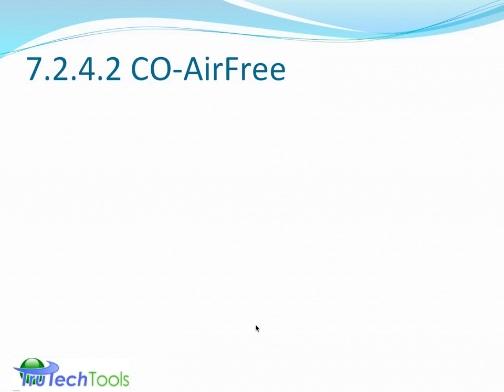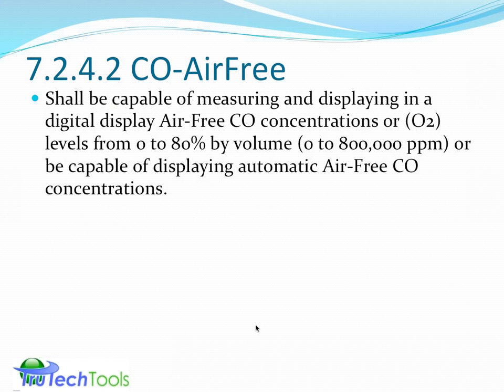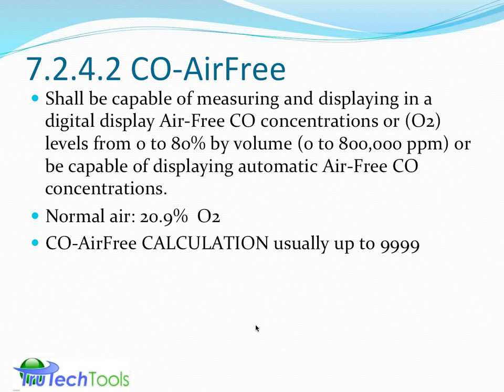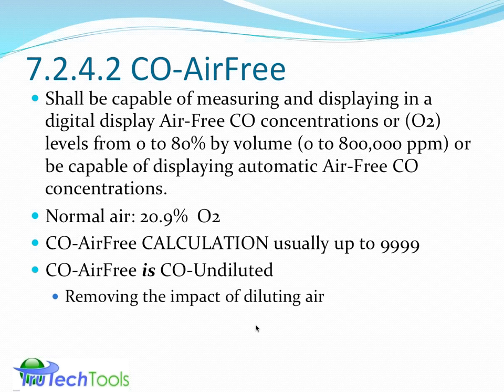There's another part of the standard which requires 7.2.4.2, CO air-free measurements. Here's information lifted directly from the standard: shall be capable of measuring and displaying on a digital display air-free CO concentrations directly. Since normal air has a concentration of 20.9% oxygen, the CO air-free calculation, by my math, and I've done product development and have some patents on different products, usually says we're looking at values up to about 10,000 parts per million in the calculation. So I'm pretty sure that statement that's lined out there will be lined out from the final version of the standard.